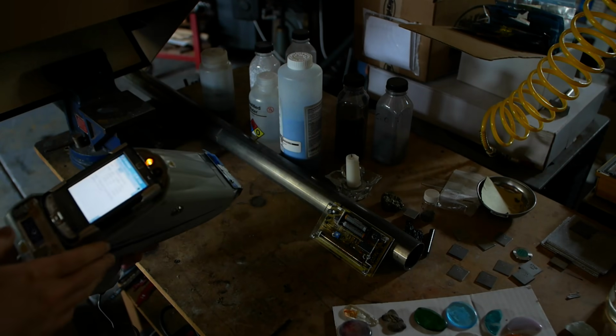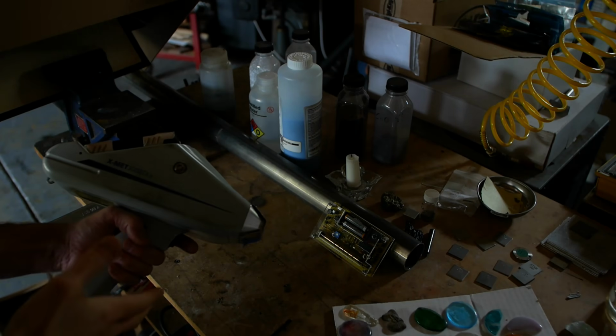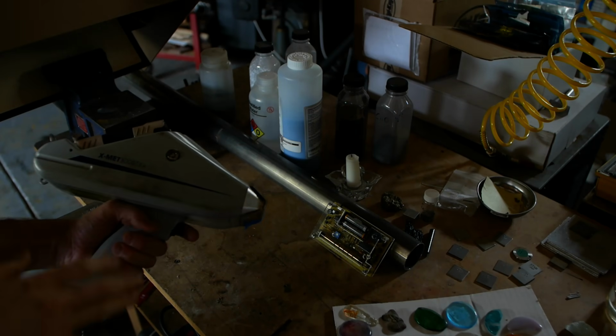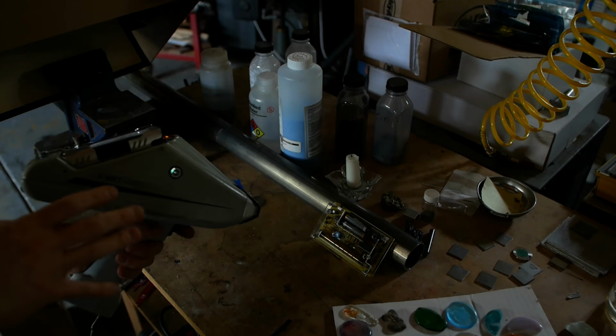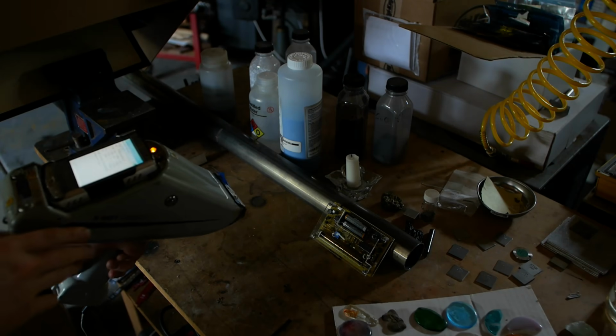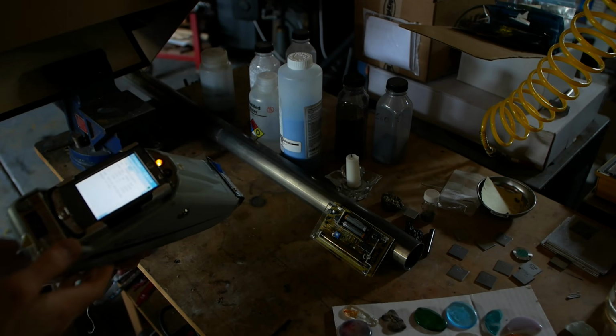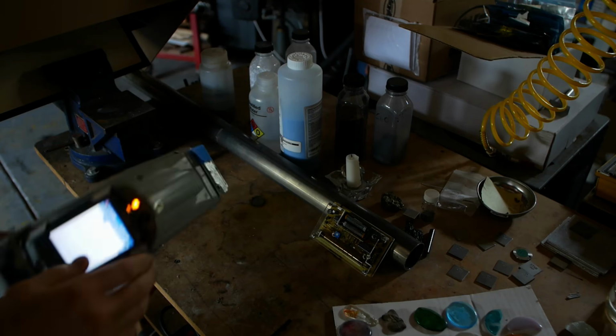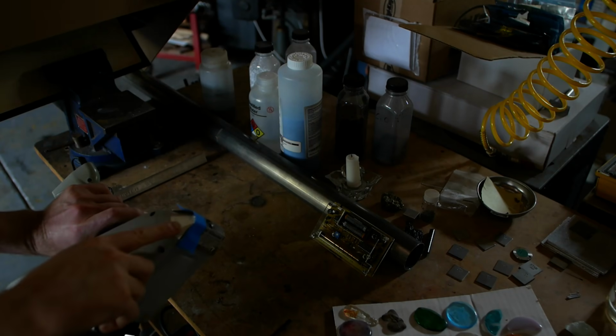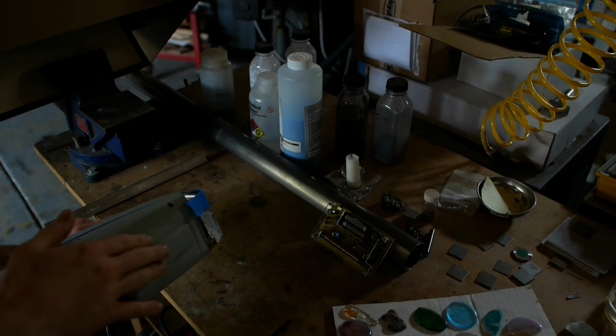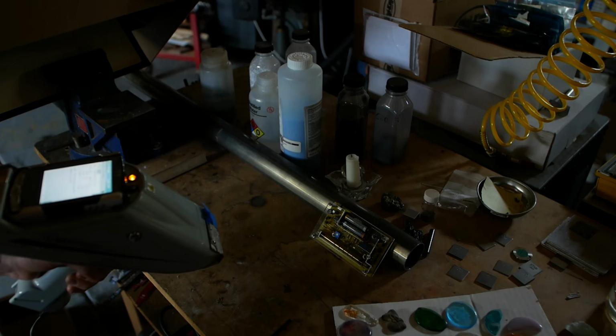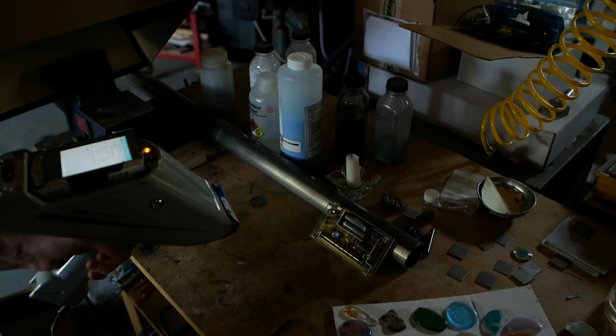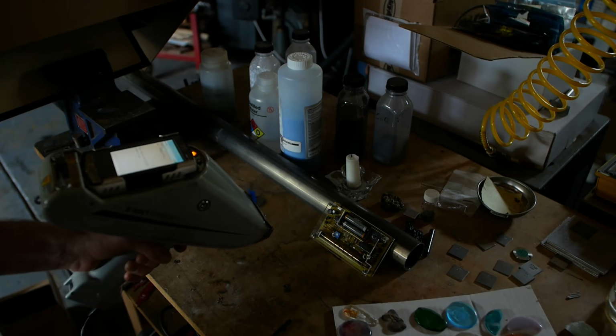Let's talk about what this machine actually emits. It's true that you wouldn't want to turn this on and take a nap next to it because it does emit X-rays. But to put this in perspective, this is about 10 or 100,000 times less powerful than a typical medical imaging X-ray tube. So I've covered up this proximity sensor on the end here so that this thing will emit X-rays even when it's not butted up against an object. And I'm going to aim it at my mighty ohm Geiger counter there.